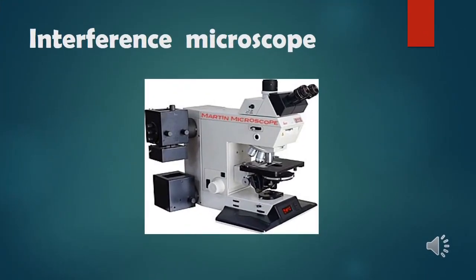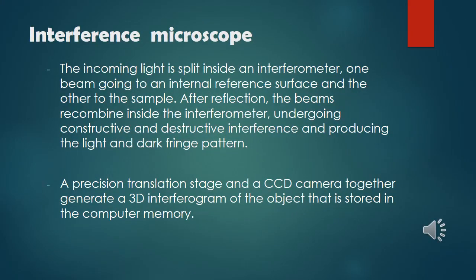Lastly, we have the interference microscope. The main function of the interference microscope is when incoming light is split inside an interferometer, with one beam going to an internal reference surface and the other to the sample. After reflection, the beams recombine inside the interferometer, undergoing constructive and destructive interference and producing a light and dark fringe pattern. A precision translation stage and a CCD camera together generate a 3D interferogram of the object stored in computer memory.